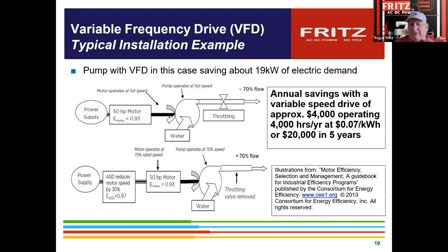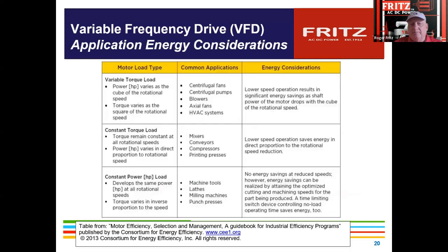So over 5 years, say about $4,000 a year in operating cost, and about $20,000 over 5 years. So it's definitely worked. Plus you have your demand reduction because you're just not running up to that 19 kilowatt anymore.